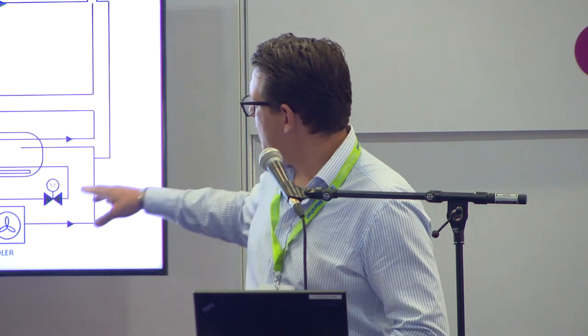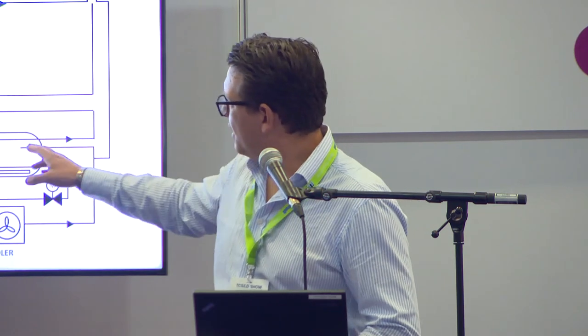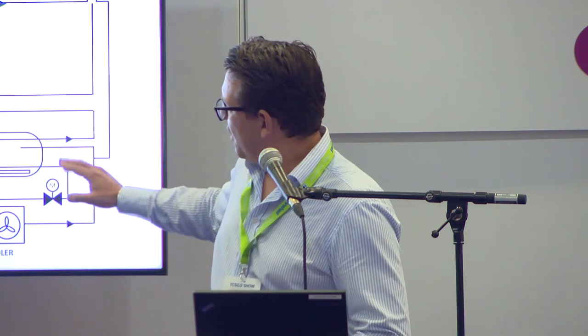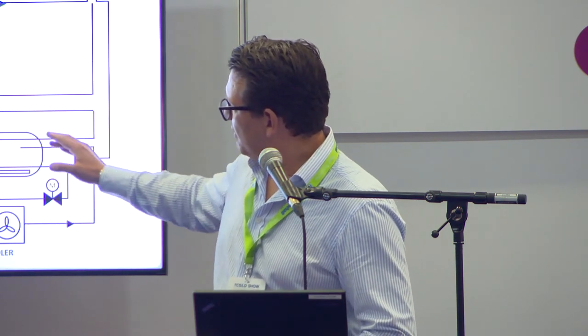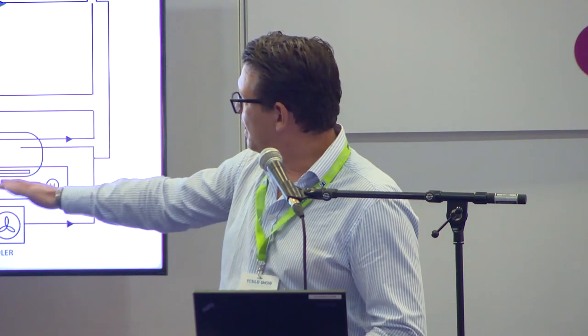I'll just run you through the schematic up here. What we have over here is the air cooler, so the component which is absorbing the heat from the room or the product. The refrigerant then goes in what we call an LPR, or low pressure receiver. At this point, this is an overflow system, so we've got a fully flooded evaporator, which is overflowing by roughly around about 5%. So we've got 5% of the mass flow rate going through this evaporator going into the LPR, which would give us some subcooling for the liquid coming into the LPR, which adds to the efficiency. With having a flooded evaporator, it means that we have a smaller component as well.